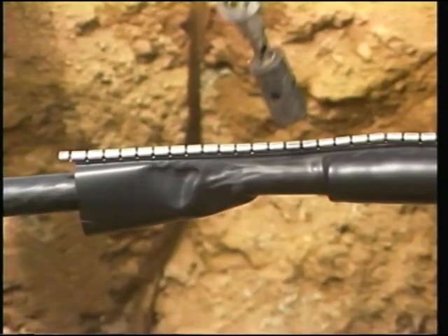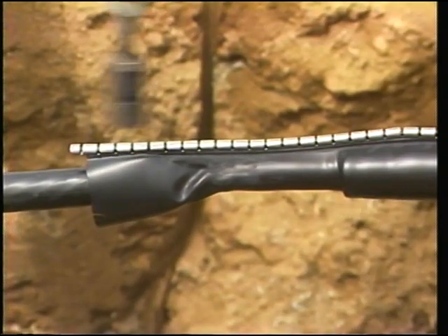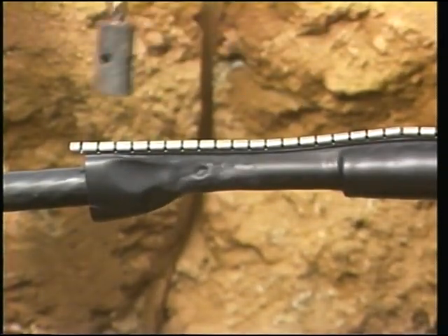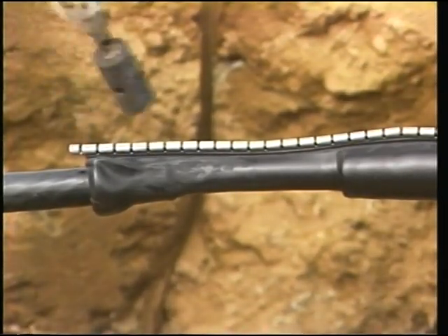Now, for the splice to be effective, it must have the same design characteristics as the original cable. This means a splice must be installed that provides the same voltage stress and static relief properties as the original cable. Now, how the cable splice is prepared depends on many things. The cable design, its type of insulation, and the type of shield can all affect the type of splice and how that splice is prepared. To make sure the workman prepares the cable correctly, he needs to use a specific set of directions.